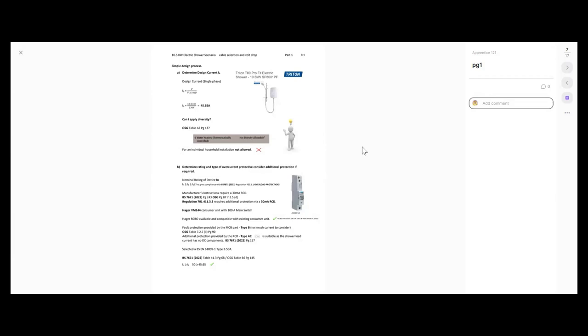That's page 137 of the on-site guide, Table A2 — all the pages and things are in the PDF so you can find those. Simple answer: can we apply diversity, can we save ourselves a few quid? No, we can't. So we've got to go with 45.65 amps. Ten and a half kilowatt — it's going to be nice and warm.